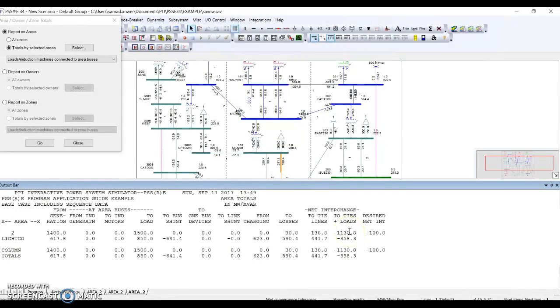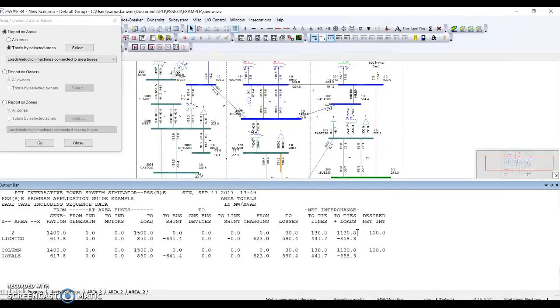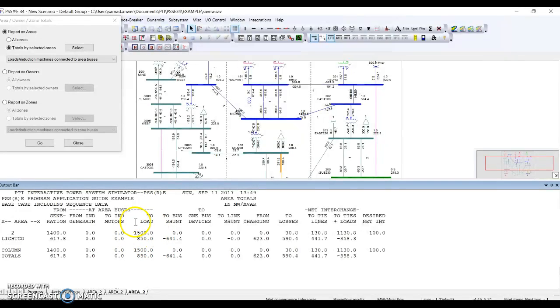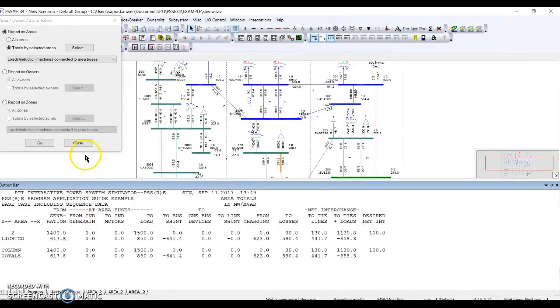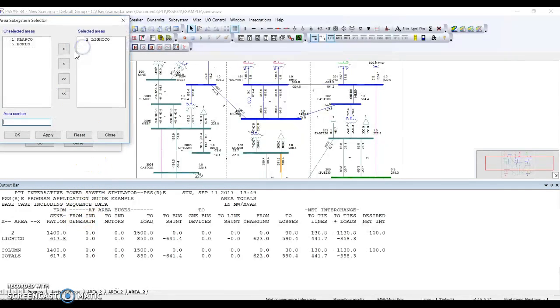The negative sign shows that it has an import. This minus sign shows it is importing 1100 megawatts to meet that load, because the load is above 1500 megawatts. If I include losses, it will go to 1530 megawatts, and my generation in this area is 1400 megawatts. You can also select two areas of your choice.